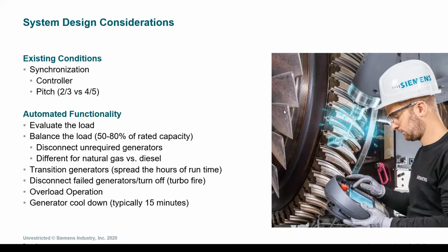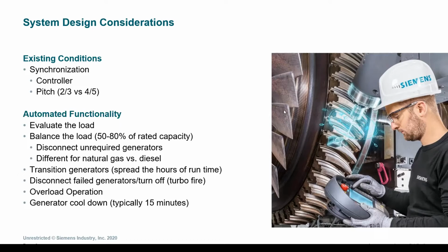Before we dive into the sequence of operation, it's important to understand what operation is already programmed into the generators. First, as soon as the generators are connected to the emergency bus, the generators automatically evaluate the load. From here, they balance the load to load up the generators from 50 to 80% of their rated capacity. They then disconnect the unrequired generators based off this loading. But it is worth mentioning that this is different for different classifications of generators, whether it's natural gas versus diesel.